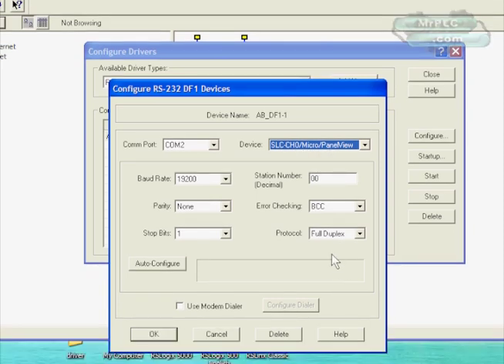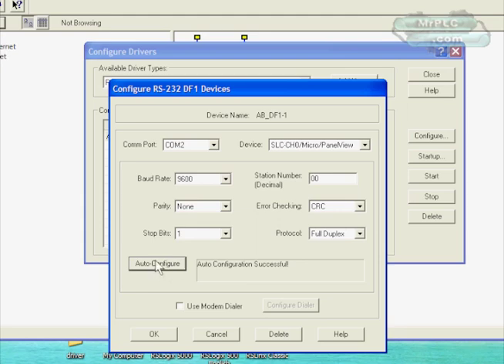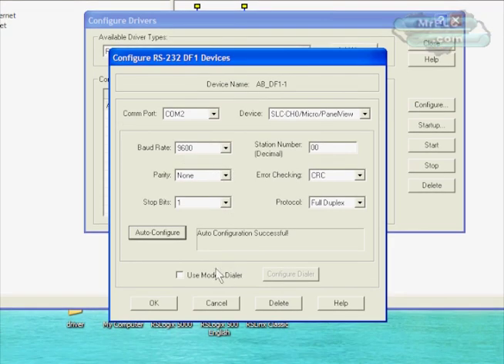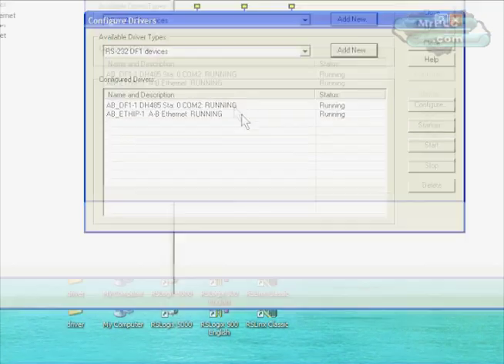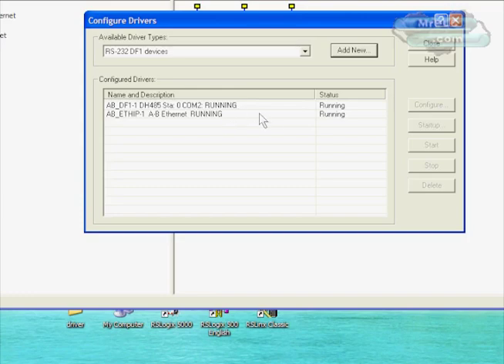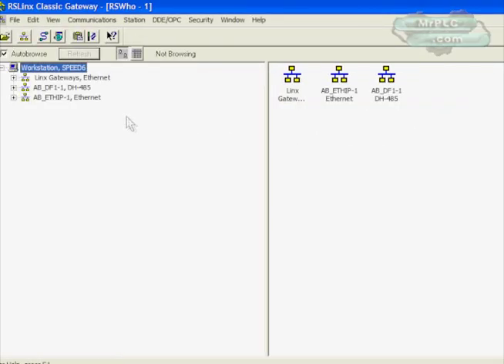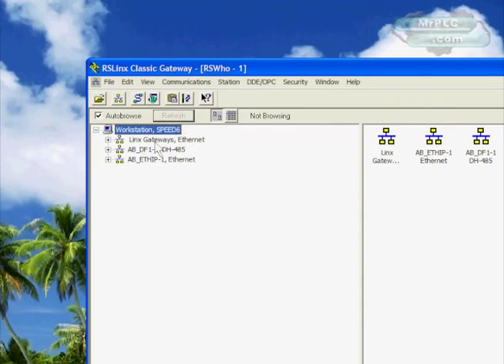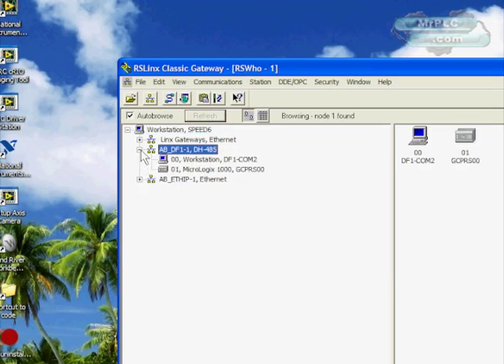Now that we know what com port we're on, we're going to choose com 2. Also we've got to pull down and choose SLC-CH0/Micro, and make sure that your cable is already connected to your Micrologix. Then we're going to use the auto-configure button to go out and have Linx query the PLC. The PLC has a default setting, this happens to be the baud rate setting, and it did find that.